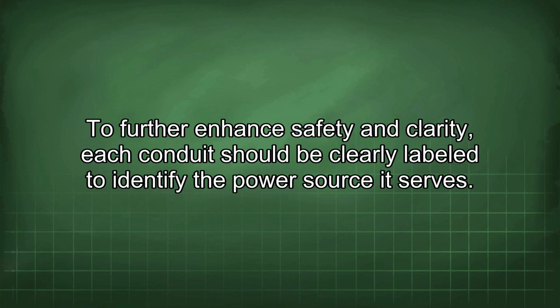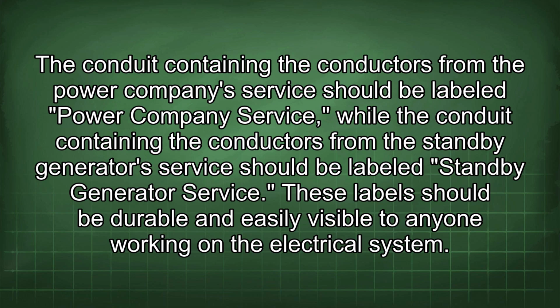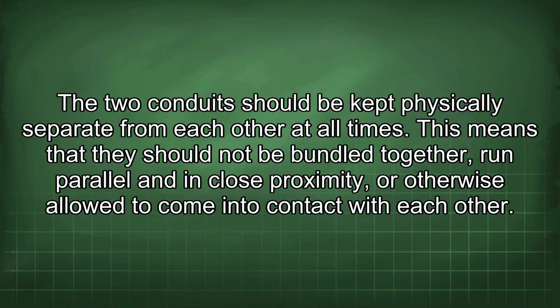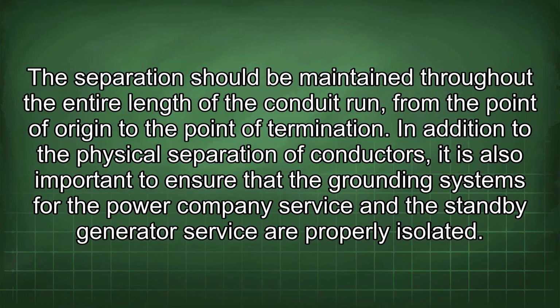To further enhance safety and clarity, each conduit should be clearly labeled to identify the power source it serves. The conduit containing the conductors from the power company service should be labeled Power Company Service, while the conduit containing the conductors from the standby generator service should be labeled Standby Generator Service. These labels should be durable and easily visible to anyone working on the electrical system. The two conduits should be kept physically separate from each other at all times. This means that they should not be bundled together, run parallel and in close proximity, or otherwise allowed to come into contact with each other. The separation should be maintained throughout the entire length of the conduit run from the point of origin to the point of termination.